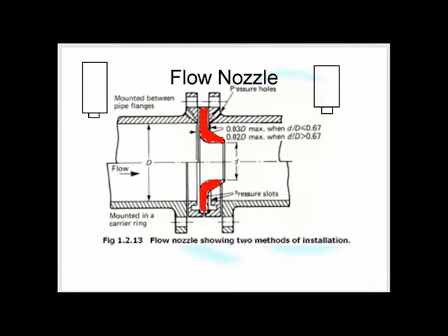And you have to push your pipe down. It's called springing the pipes. And you push your pipes down or you push your pipes up using hydraulic presses, and you hope that the flow nozzle falls out before the pipe cracks. And so it's one of these things. In theory, it should be the best of both worlds. In practice, it's a mess.